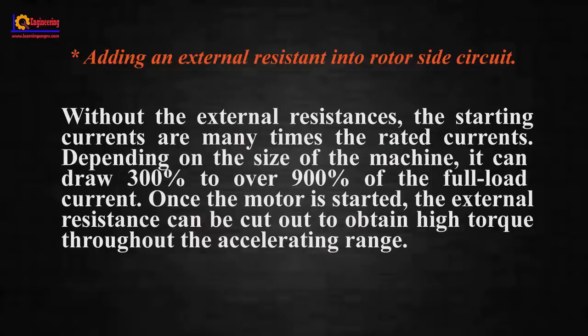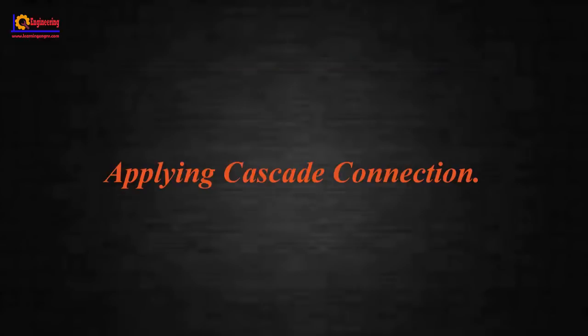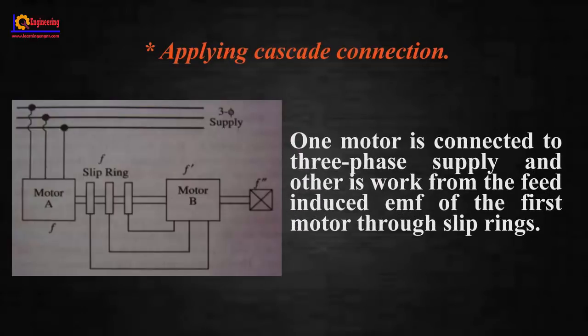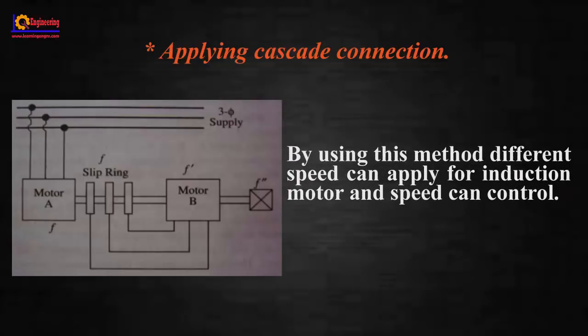Applying cascade connection: in this cascade operation method, two motors are mounted on the same shaft and run at same speed. One motor is connected to three-phase supply and the other is fed from the induced EMF of the first motor through slip rings. By using this method, different speeds can be applied for induction motor and speed can be controlled.